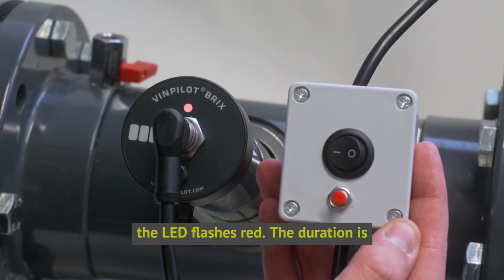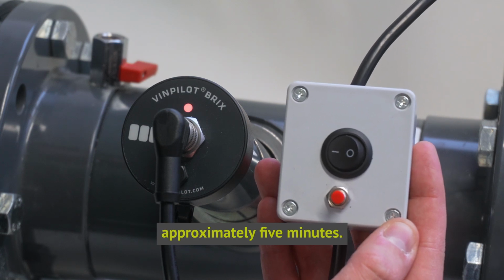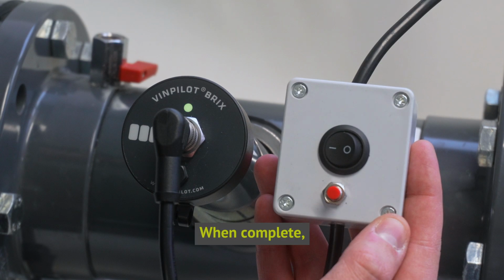During calibration, the LED flashes red. The duration is approximately 5 minutes. When complete, the LED turns solid green. 0 Brix is now calibrated.